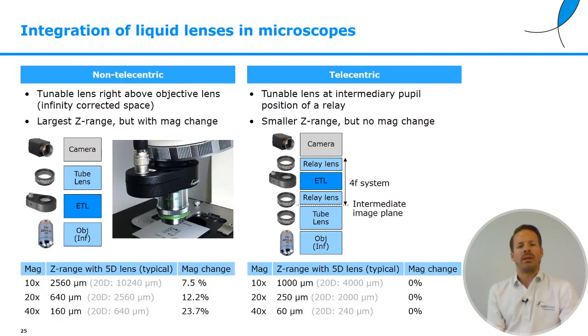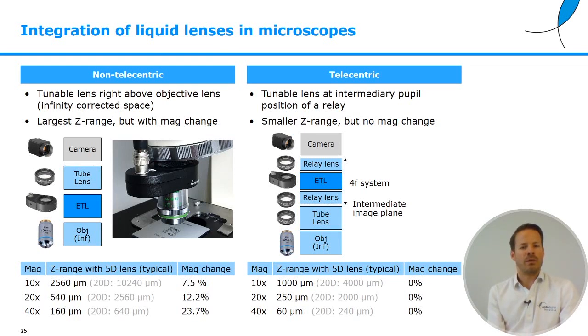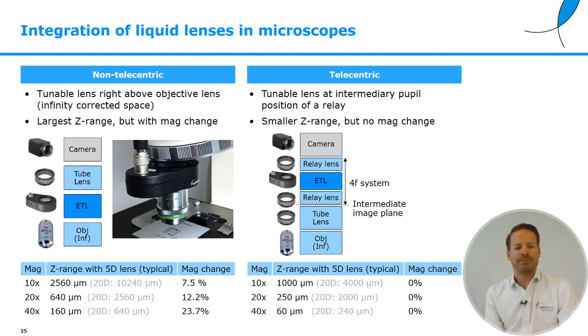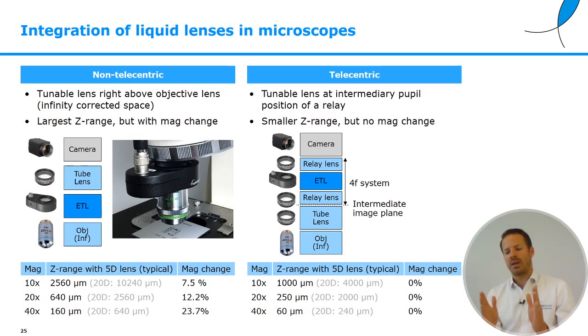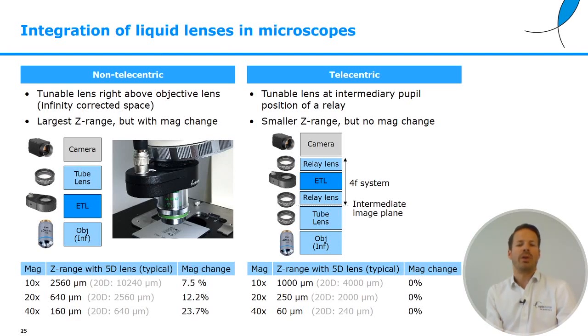For microscopy, there are two main situations. In a non-telecentric approach, you place the liquid lens right above the objective in its infinity space — pretty straightforward, sometimes with the right threading, such as M26 for Mitutoyo lenses. You get rather large Z ranges; for example, a 160-micron Z range for 40x magnification. However, because you are also bending the chief rays, you get some magnification change which can be significant — about 23–24% over the whole 160-micrometer range of a 40x lens.